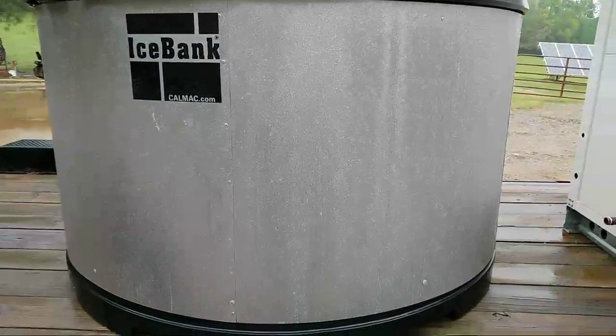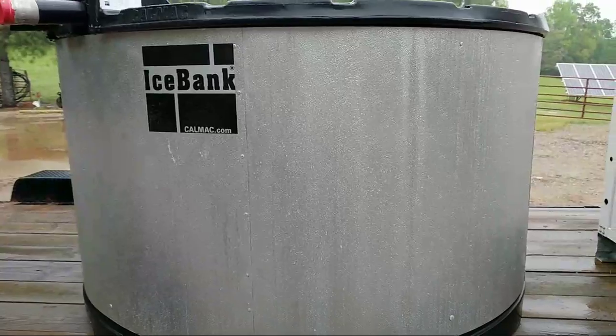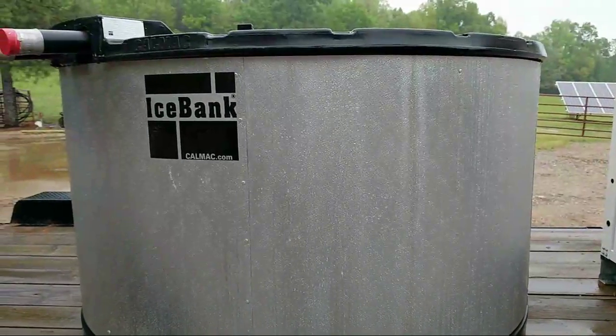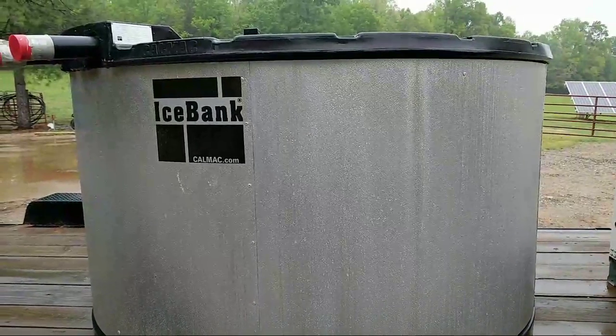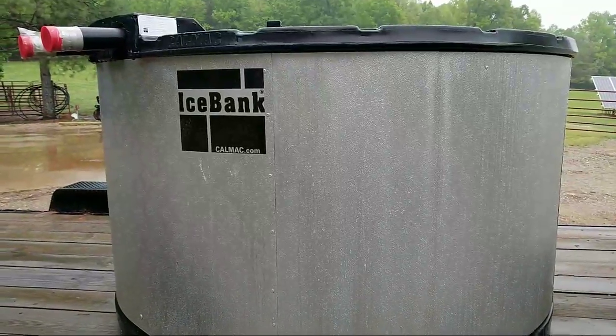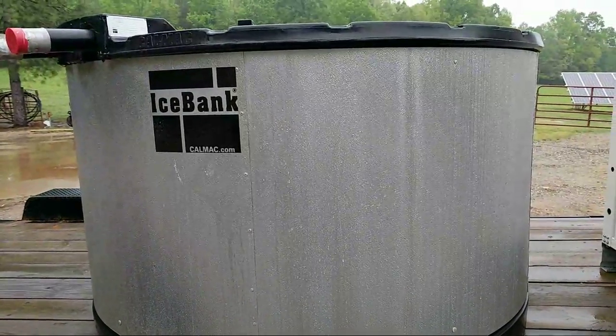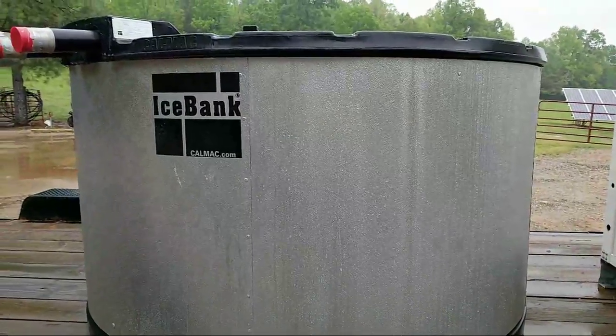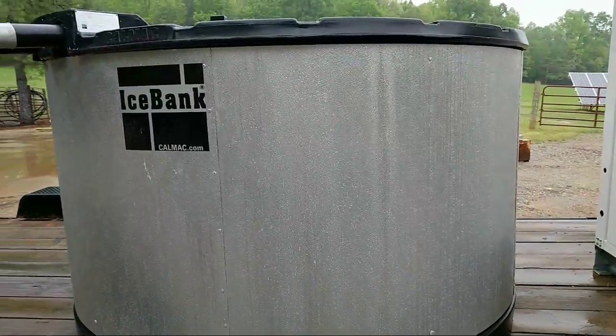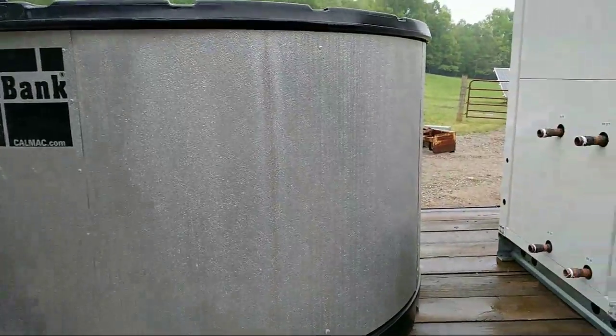That's the goal. It has PEX pipes inside that will have propylene glycol in them, about a 30% mixture of water and propylene glycol. We'll be able to bring that glycol down to about 20 degrees Fahrenheit and freeze this tank solid. We're going to do that with solar.